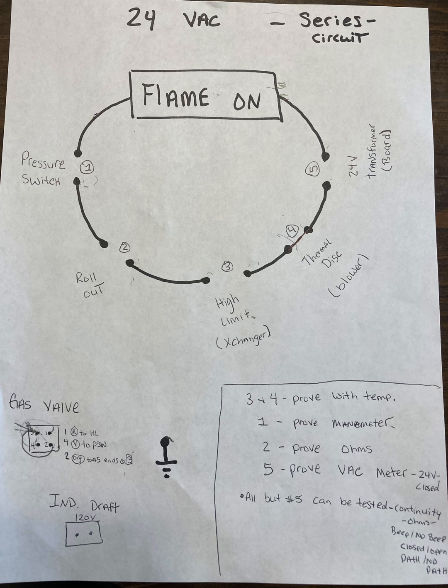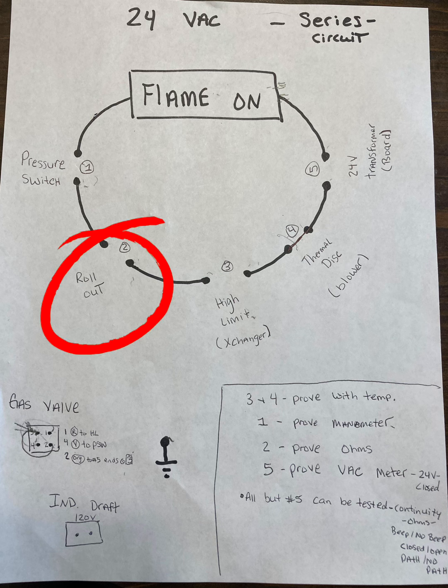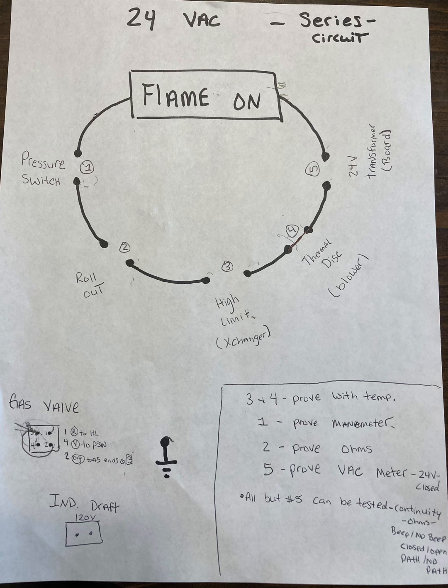Moving on. Up next on our list are the rollout switches. Our 24 volts are coming into it and coming out of it. These are activated when the flame rolls out and it gets too hot. It's a resettable type deal. There's a little nipple on it. You can press it, it clicks and it closes. We don't like to do that.